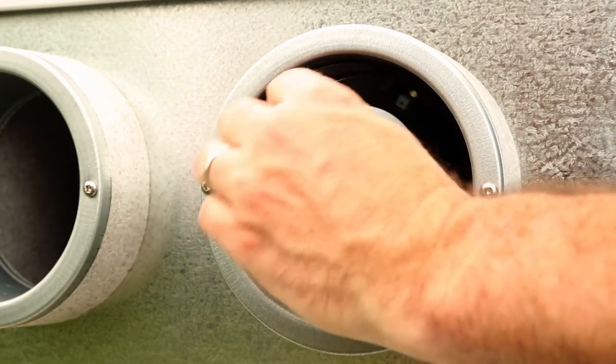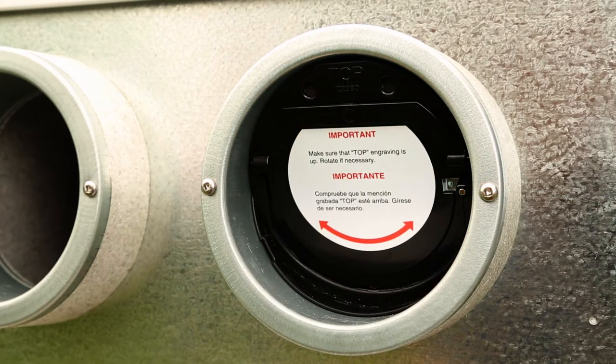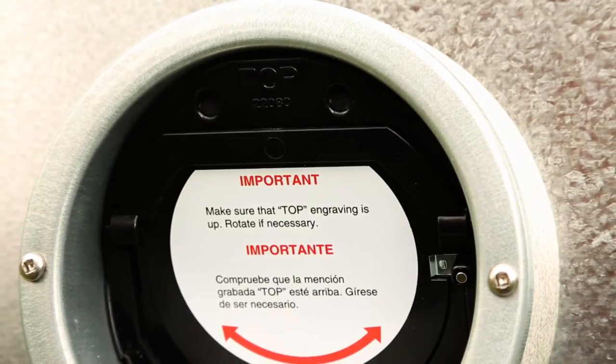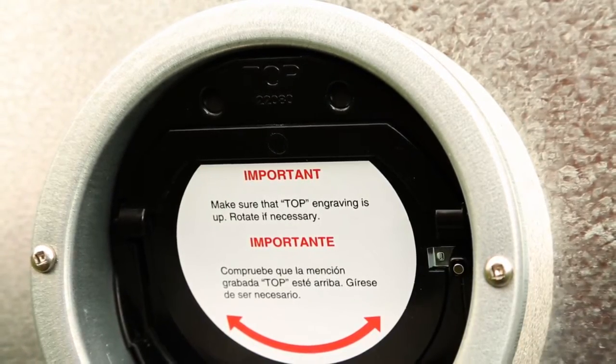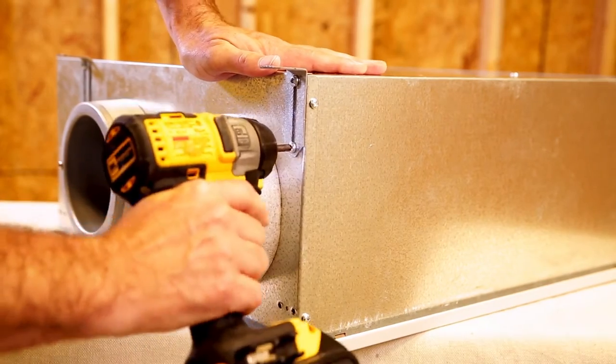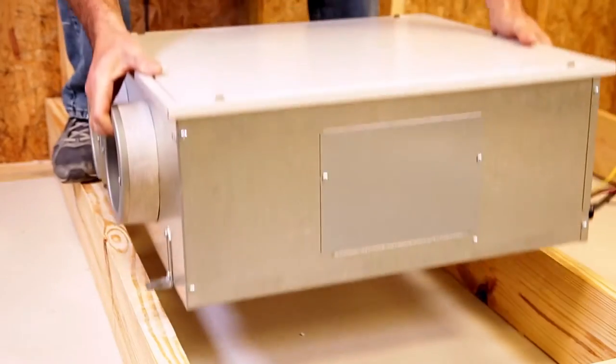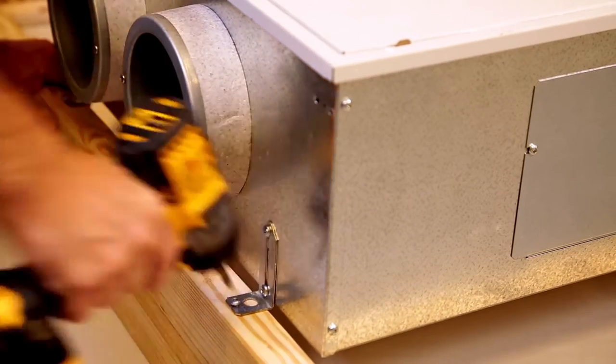To install the ERVS-100 in the attic, first rotate the backdraft damper 180 degrees so that it falls in the closed position and the word top engraved on the damper is facing up at the top. Mount the brackets to the bottom corners of the unit using two number 10 by 5 eighths inch screws per bracket. Secure the unit to the top of the trusses using one number eight by one and a half inch screw for each bracket.